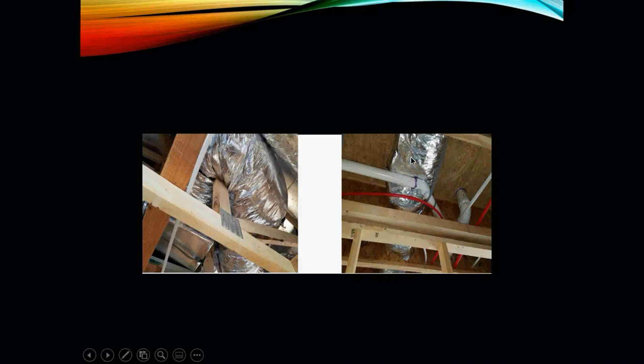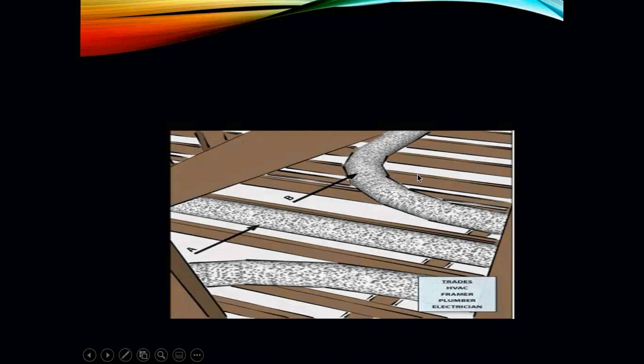Seeing stuff like this where flexible duct is crushed because of a drainage line or something like that, that's no good either. In that particular area, that flow is being reduced. That doesn't work very well. So when we are installing our ductwork, we want to have as few bends as possible. If we have to make bends, we want them to be nice and gradual. Okay, we don't want to extend the connections greatly. We want to try to keep them as short as possible, but we don't want to have massive changes in direction.